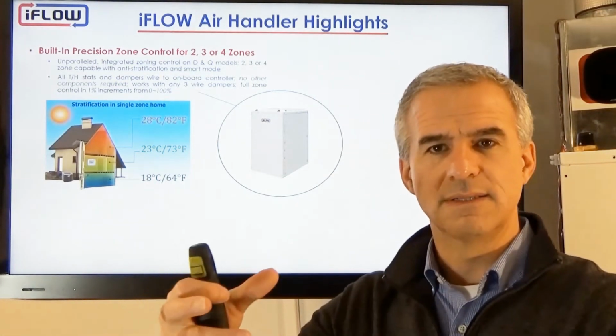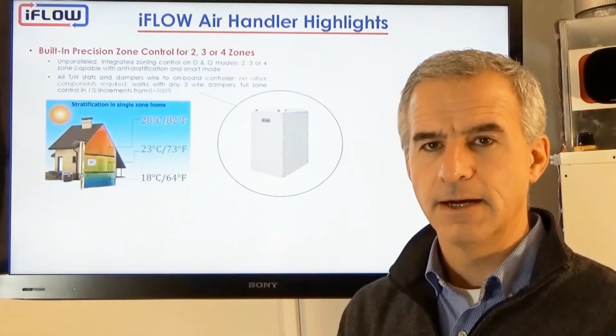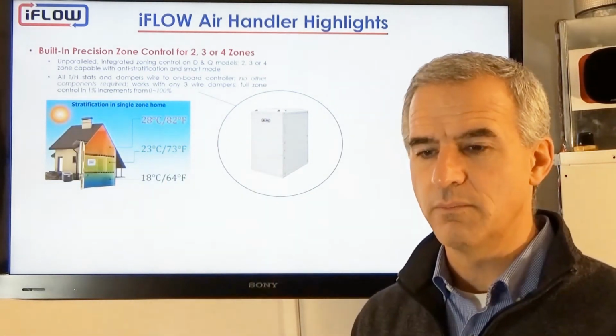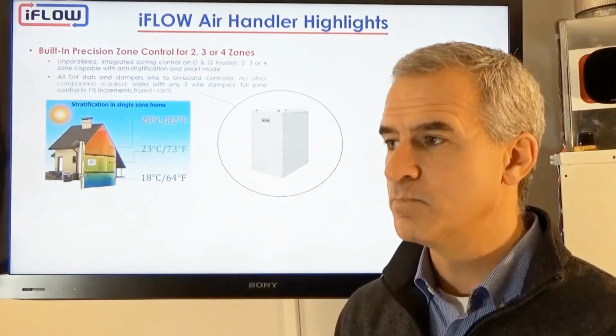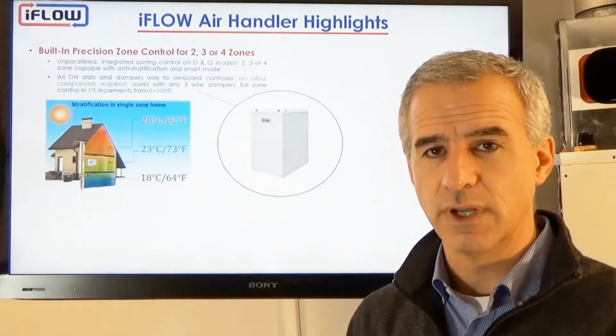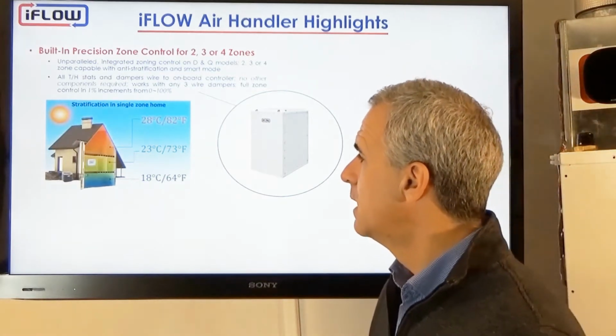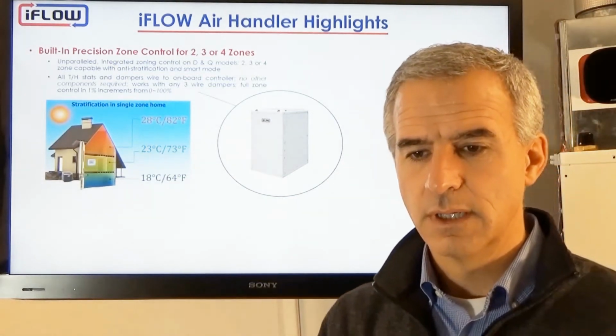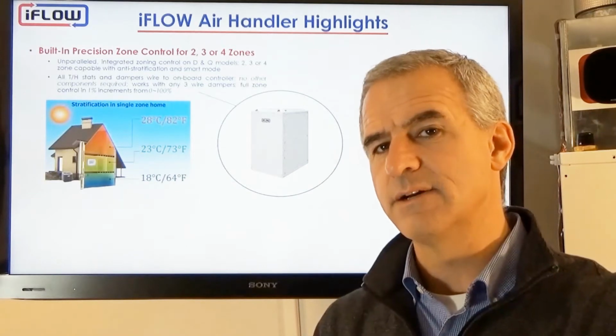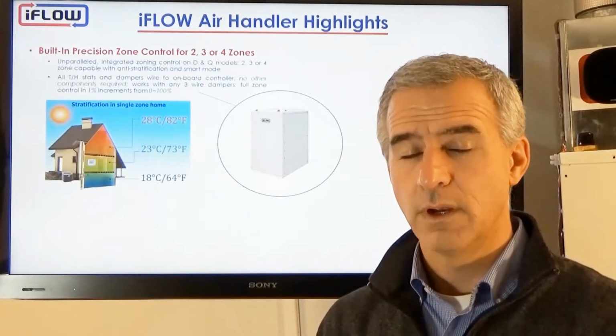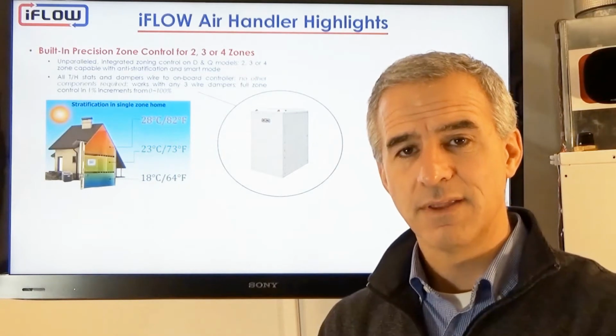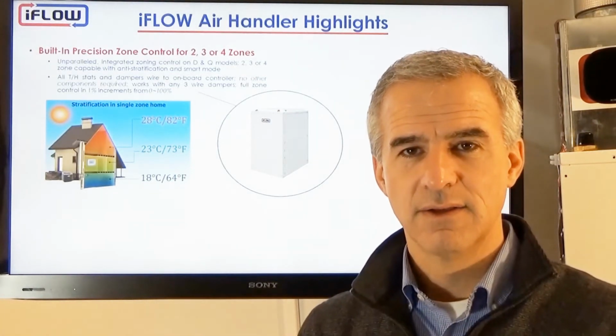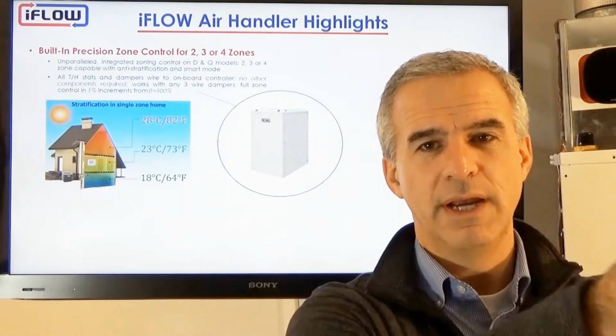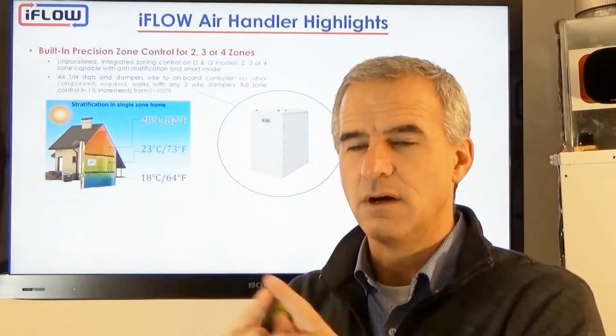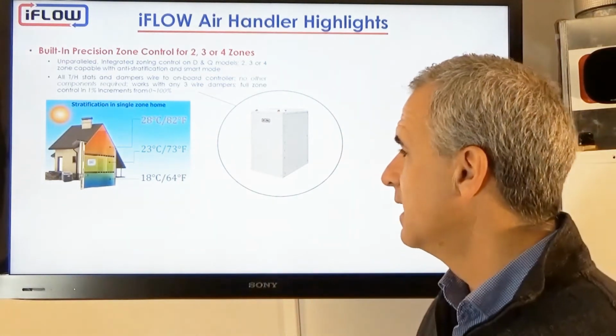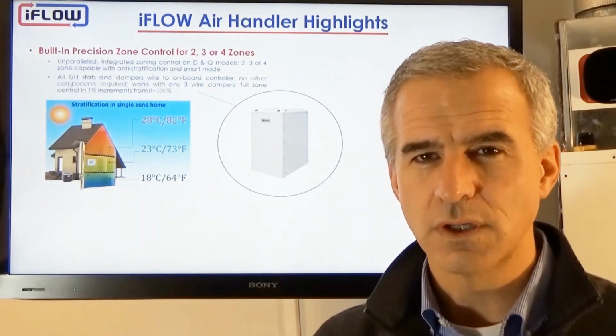If the trunk line, let's say, goes left and right, we can put a damper on each side. So in a home that may not have had zoning previously, we can go in and retrofit zoning to deliver more comfort. We can go with 2, 3, or 4 supply lines out and with a common return, or we can go with 3 or 4 supply lines out and then 3 or 4 return lines back. So then we can pinpoint and deliver supply and return to each zone. That would be the ultimate in comfort, ultimate in design. So that would be for mostly new construction.